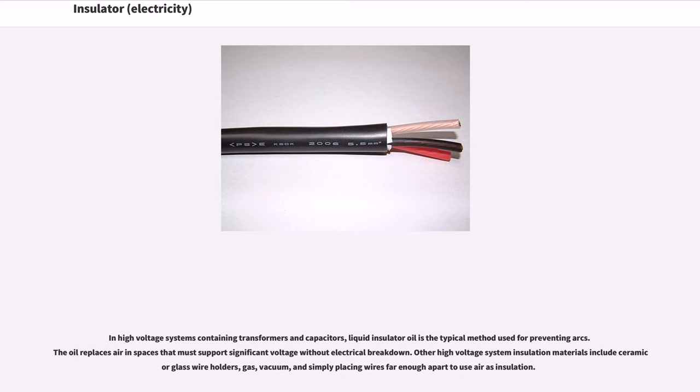In high-voltage systems containing transformers and capacitors, liquid insulator oil is the typical method used for preventing arcs. The oil replaces air in spaces that must support significant voltage without electrical breakdown. Other high-voltage system insulation materials include ceramic or glass wire holders, gas, vacuum, and simply placing wires far enough apart to use air as insulation.